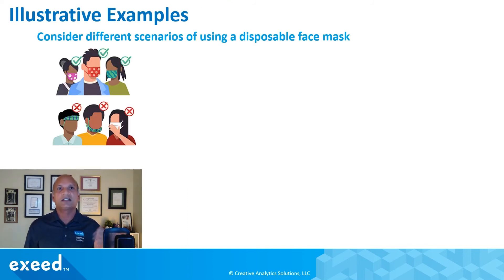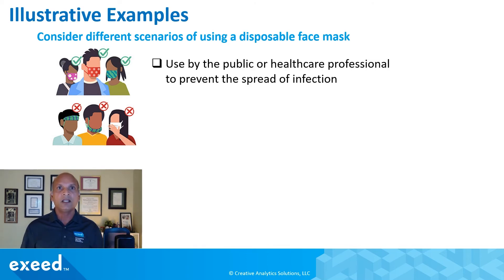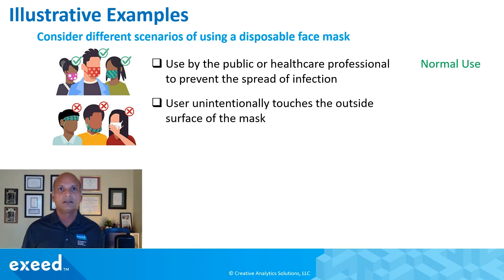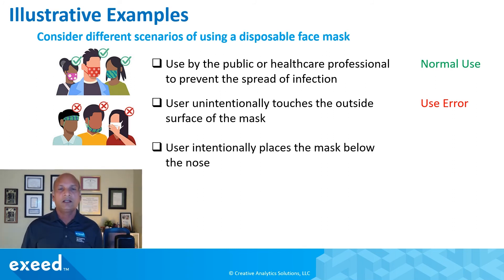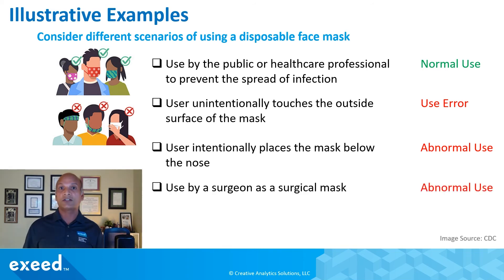Here are some examples using a face mask, very relevant for COVID-19. The purpose of a face mask is to prevent the spread of infection, so use by the public or healthcare professionals for that purpose is normal use. If a user unintentionally touches the outside surface of the mask — which can be contaminated — that's a use error; it's very normal human behavior. If a user intentionally places the mask below the nose, that's abnormal use, as we see quite frequently. And if a surgeon decides to use this mask in an operating theater, that is also abnormal use.